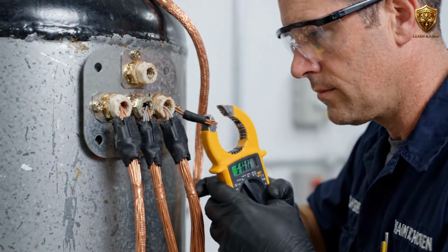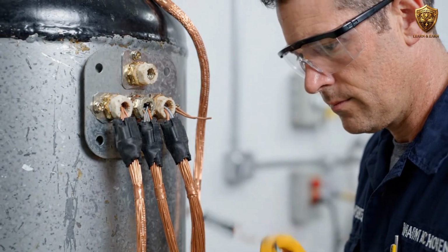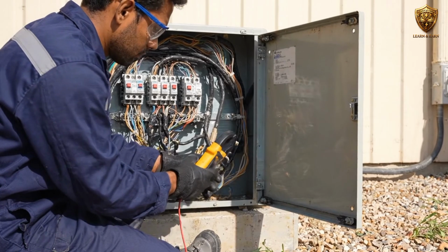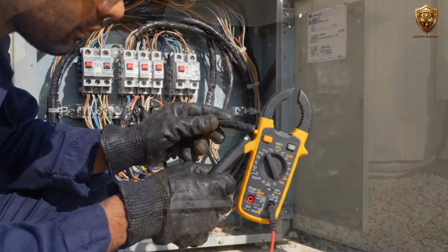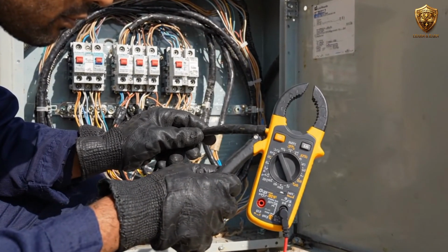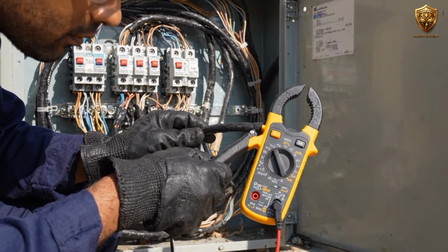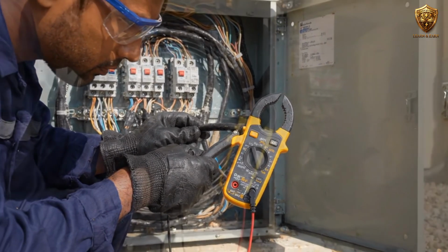Compressor electrical testing also requires careful attention to safety and the manufacturer's procedure. The compressor terminals normally have defined electrical relationships, and the technician can use appropriate resistance and insulation tests to evaluate the motor windings and possible faults. A compressor that is shorted to ground is a serious condition and normally requires further professional evaluation and replacement planning.